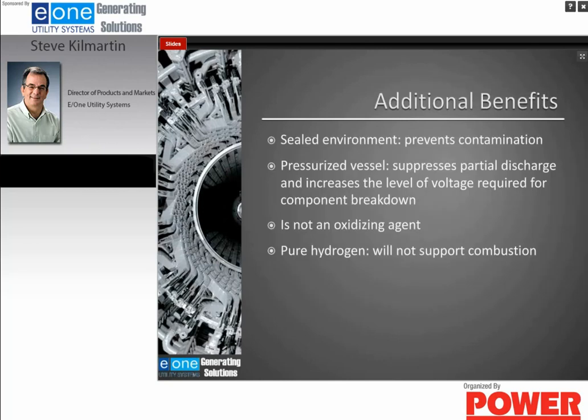There are additional benefits for using hydrogen. Because the generator has to be sealed, because the hydrogen has to be kept inside the generator, you have a sealed environment. So this prevents contaminants from entering into the generator. Contaminants such as coal dust, sand, moisture. Also, because it's a pressurized vessel, it suppresses partial discharge and also increases the level of voltage that is required for a component to break down.